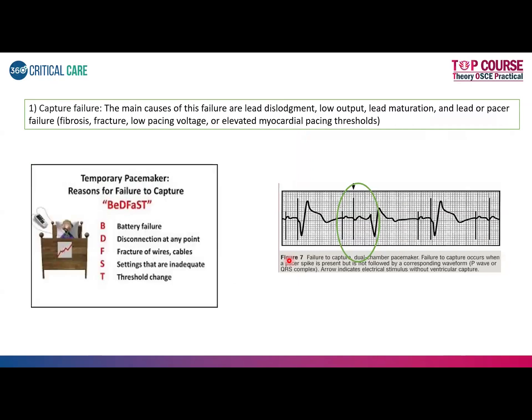Capture failure. So the main problem, you can remember the capture failure as BED FAST. What is BED FAST? Battery failure, disconnection at any point, fracture of the wires and cables, settings which are inadequate, or any threshold change which can lead to a low output state.